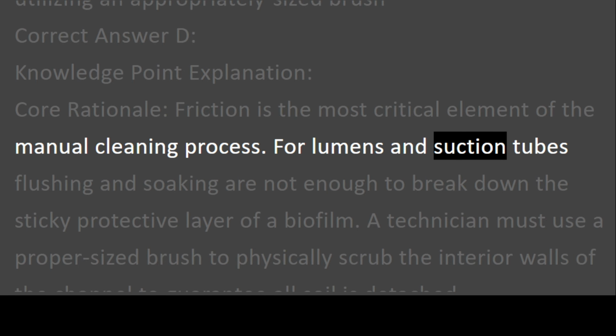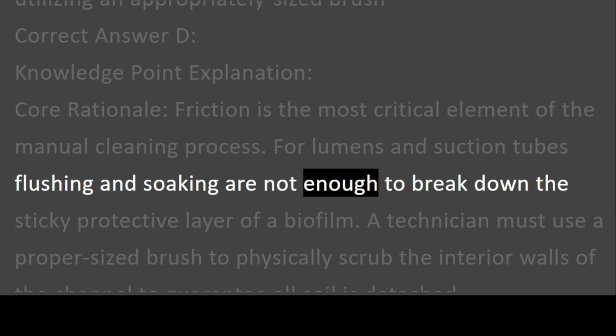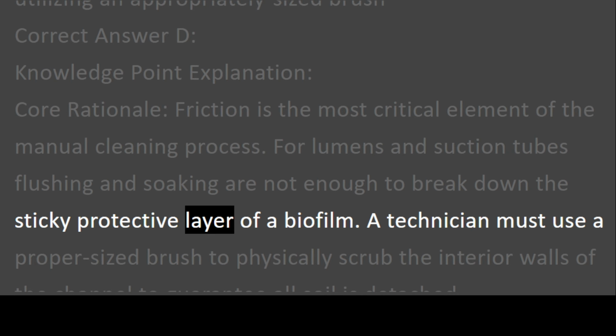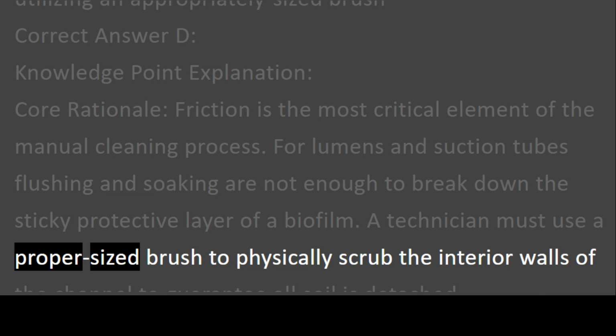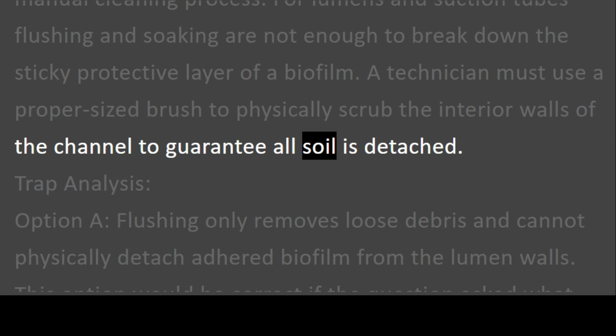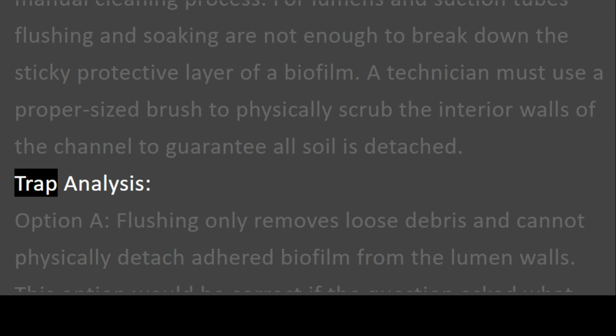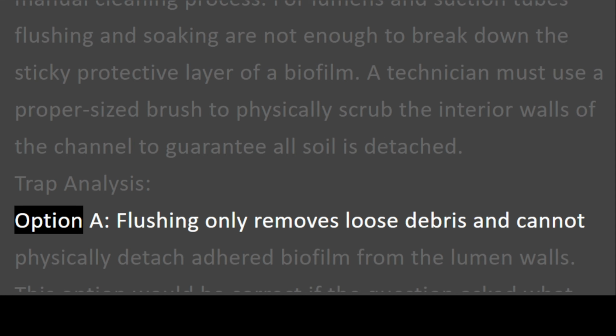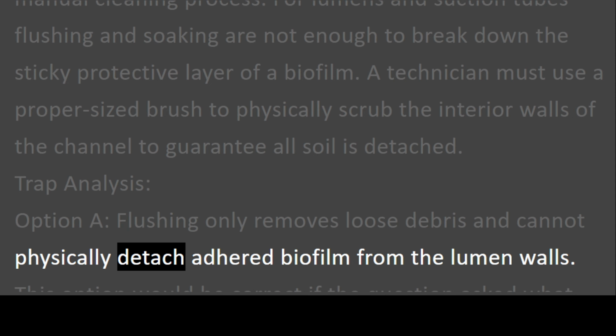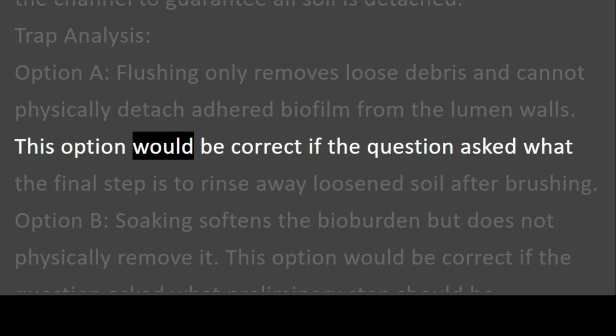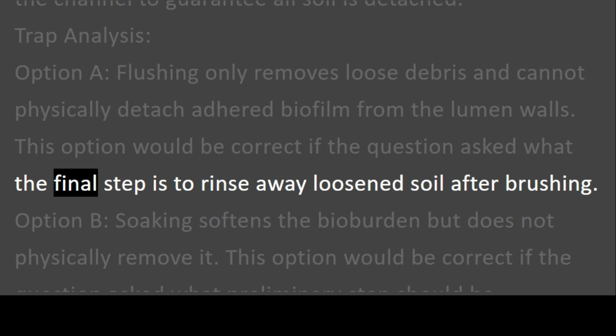For lumens and suction tubes, flushing and soaking are not enough to break down the sticky protective layer of a biofilm. A technician must use a proper-sized brush to physically scrub the interior walls of the channel to guarantee all soil is detached. Trap analysis. Option A. Flushing only removes loose debris and cannot physically detach adhered biofilm from the lumen walls.